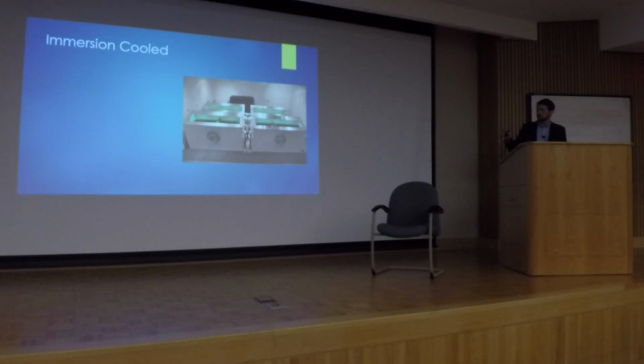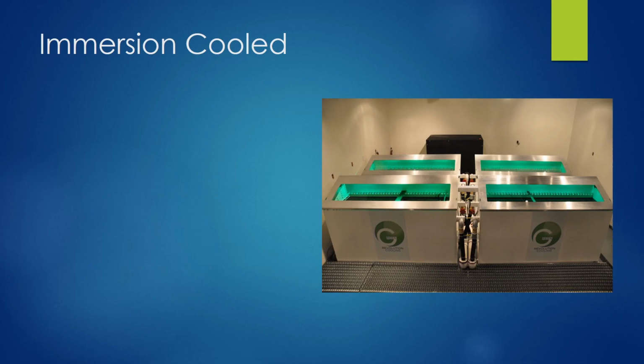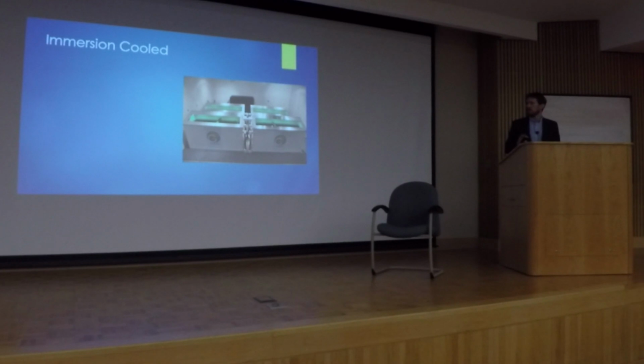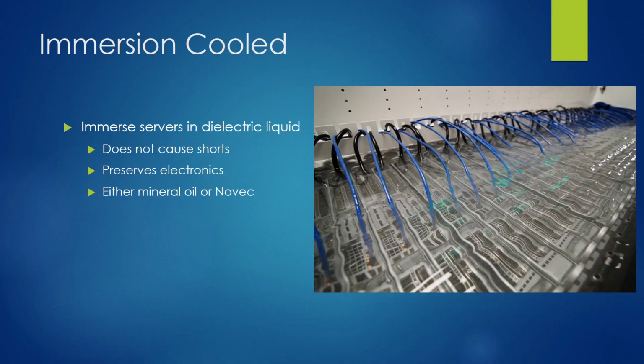Moving on from liquid cooled, this is one of the things I'm most interested in personally: immersion cooling for servers. These are vats filled with dielectric fluid, in this case non-conductive mineral oil. You take the server and dip it down into the oil, and the mineral oil conducts the heat off the server chips directly, then pumps it through a heat exchanger which can be cooled by a cooling tower outside.